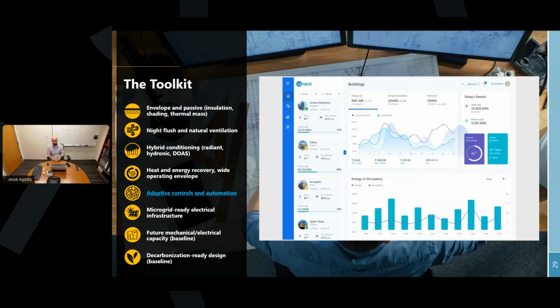We can alter comfort bands, i.e. change thermostat set points in spaces that are less occupied than others by looking at occupancy levels within a building, so that we're prioritizing where people actually are in the building to maintain comfort. And then we can also do demand-based staging of different chillers or other systems in the building based on the expected weather data that allows us to get ahead of that heat wave coming in instead of being reactive to it later on.